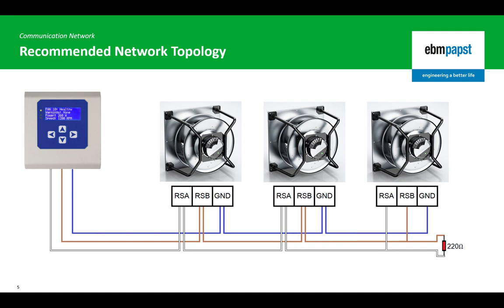Initialise the RS485 network and find the fans. The RS485 network should be laid out in bus topology, with each device connected in a chain from the controller to the first device and through to the last.